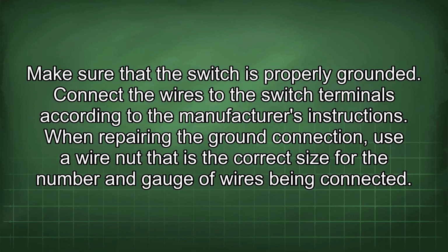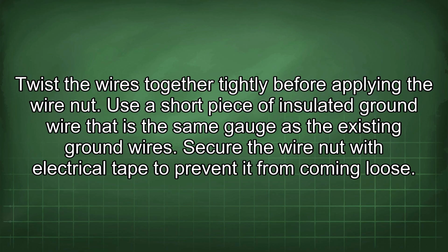When repairing the ground connection, use a wire nut that is the correct size for the number and gauge of wires being connected. Twist the wires together tightly before applying the wire nut. Use a short piece of insulated ground wire that is the same gauge as the existing ground wires. Secure the wire nut with electrical tape to prevent it from coming loose.